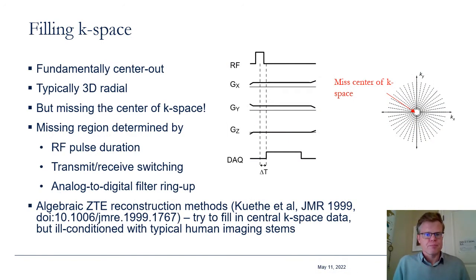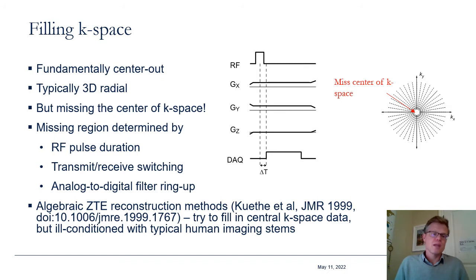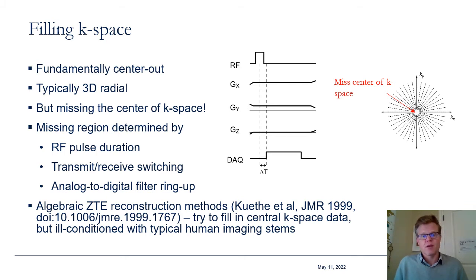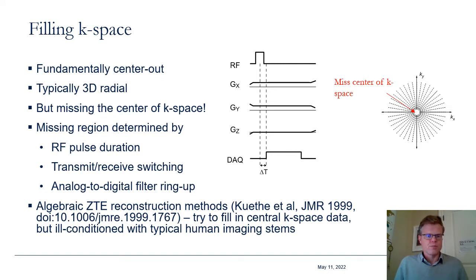Returning to the fundamentals of filling k-space in ZTE: ZTE is a fundamentally center-out k-space sampling sequence, typically done with 3D radial. The main limitation is that we are missing the center of k-space due to the dead time between the RF pulse and when data acquisition begins. This dead time is determined by the RF pulse duration, how fast the scanner can switch between transmit and receive, and associated filtering and ringing-up times. One early approach to correct this was algebraic ZTE methods, using a signal model to fill in the center of k-space, but this is not widely used because it is typically ill-conditioned with the dead times on typical human imaging systems.